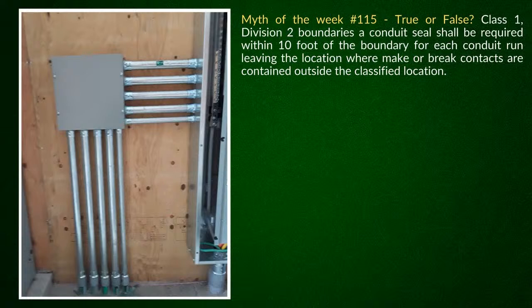One of the inspectors out in the patch said we had to have a seal off anytime we went underground because we were changing location. For example, if this is a Class 1 Div 2 area, and we were exiting that Class 1 Div 2 area and entering another Class 1 Div 2 area, we would not need conduit seals, because we're going from the same classified location to the same classified location. That would need conduit seals regardless of whether you go underground or not.